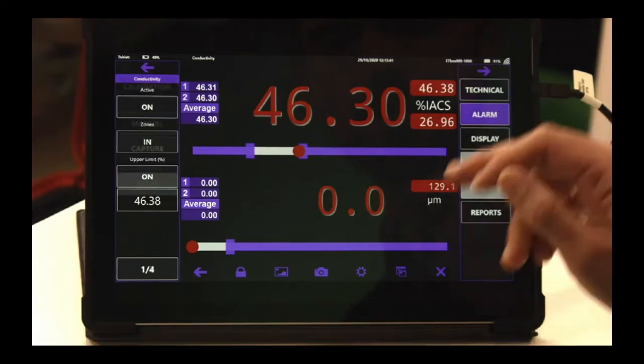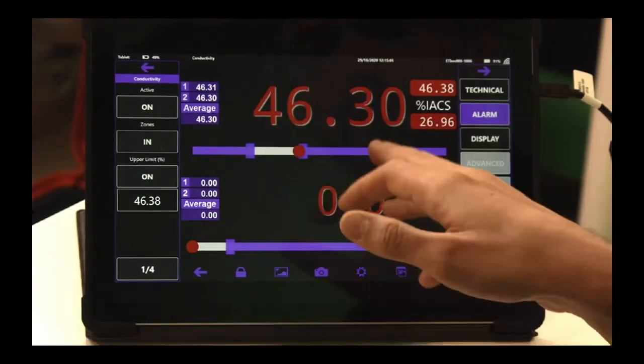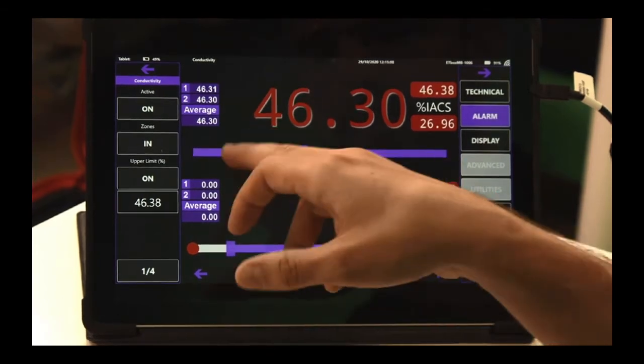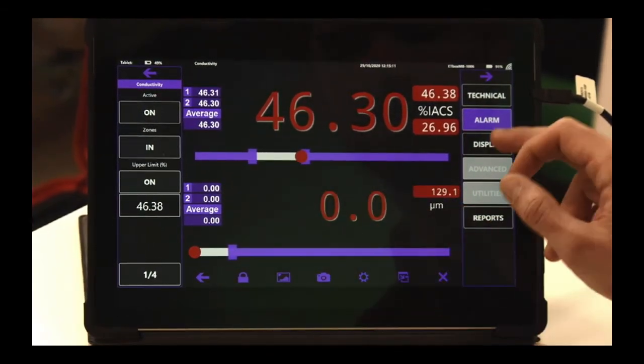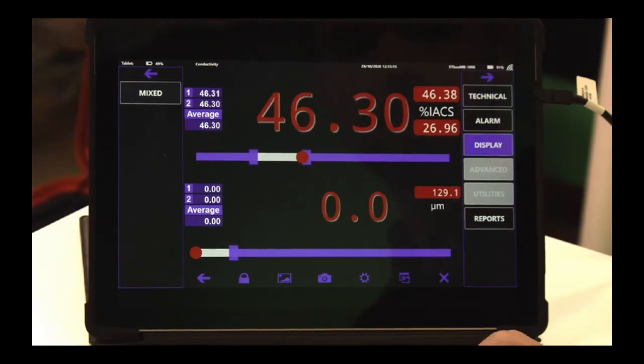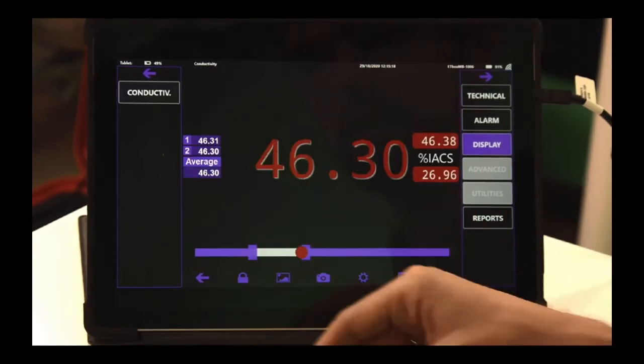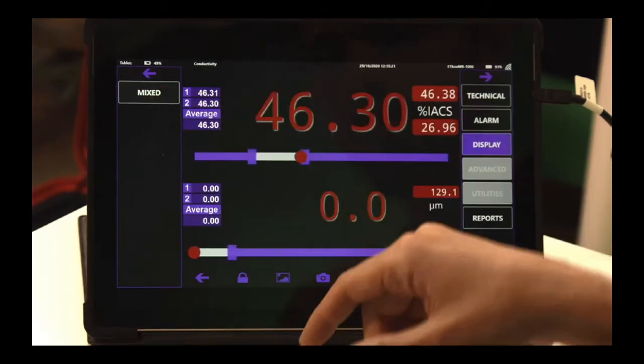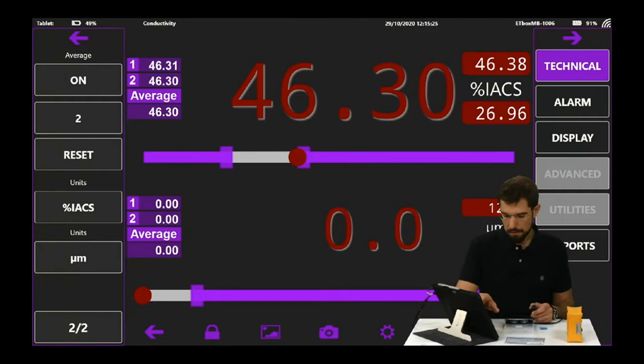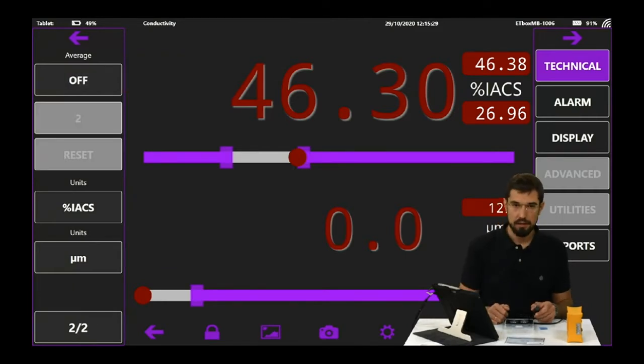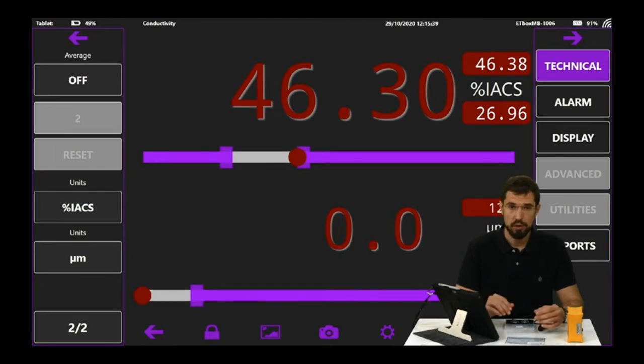On the other side, we also have an alarm set up. In this case, they've already activated, and we can see that the alarms go off when they're out of range. We also have the opportunity to change the display, but here we can only change between conductivity, thickness, or see both measurements. We have the chance to generate reports as well, but we'll see that later. This would be a general example of how to perform a combined inspection of conductivity and thickness. It should be noted that all of the algorithms used that back up the calculations of these tests have been subjected to thorough accuracy tests in order to ensure they are compliant with the most common demanding guidelines.